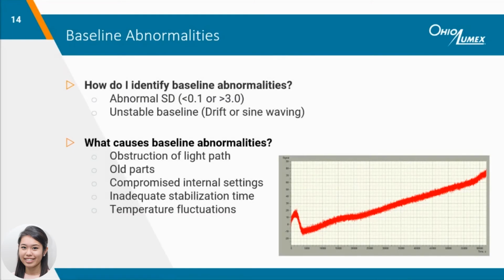Baseline abnormalities are common during the initial stabilization period and are generally easy to identify by zooming into the baseline along the y-axis. We don't recommend beginning analysis until the baseline has stabilized, which typically requires a minimum warm-up time of 2 hours from turning on both the spectrometer and pump station. We'll discuss the potential causes of baseline abnormalities and when to decide it's time to send in the instrument to Ohio Lumex.